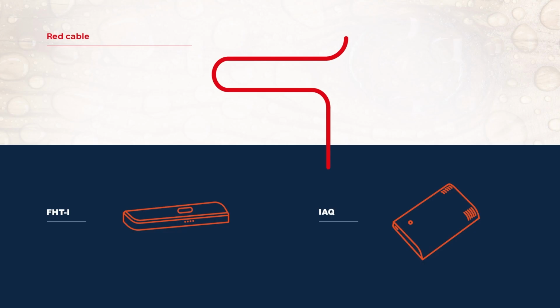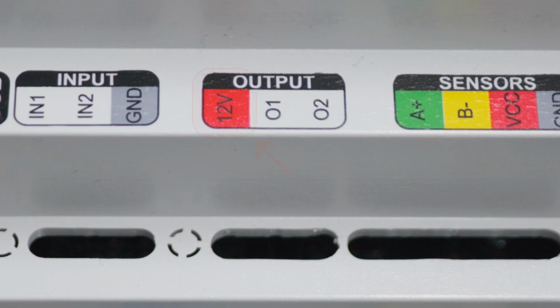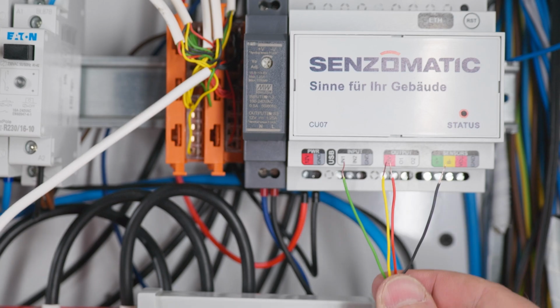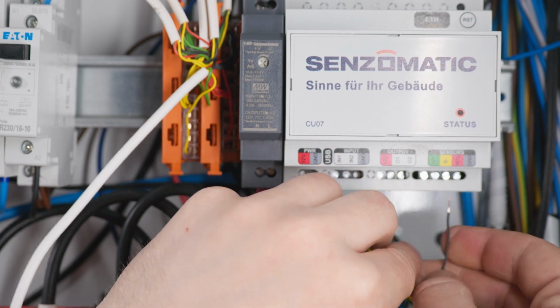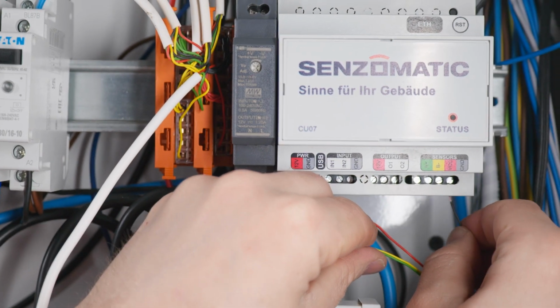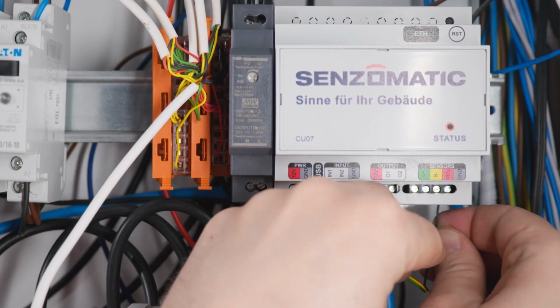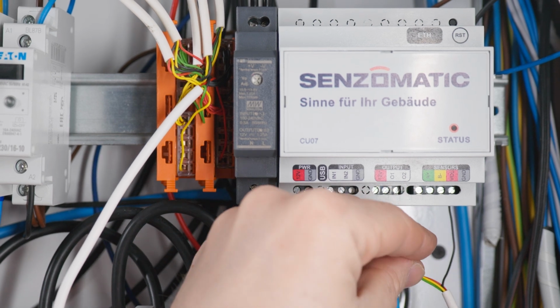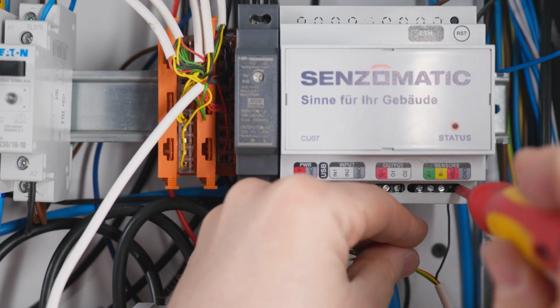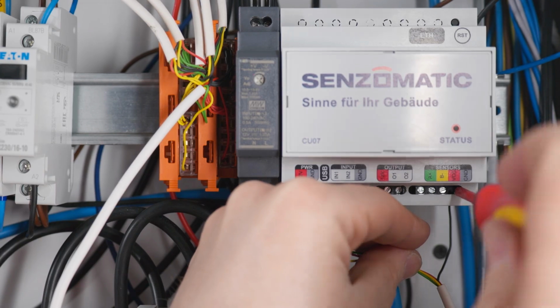The exception is the red wire from the FHT-I and the IAQ sensors. These red wires belong separately to the terminal marked 12V. Please be sure to carefully follow the wiring diagram. If you are not sure which cable in the bundle is which, connect it to the unit individually and test it. This will help you to identify which sensor is currently connected.